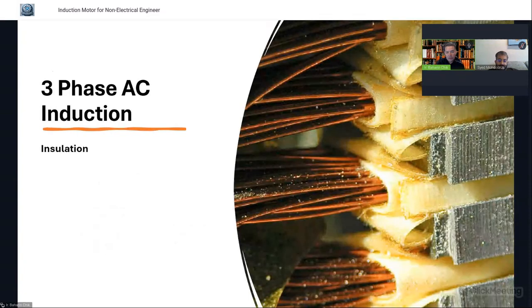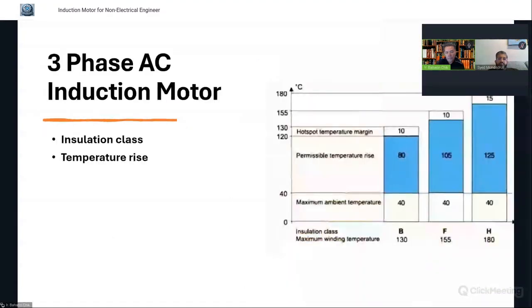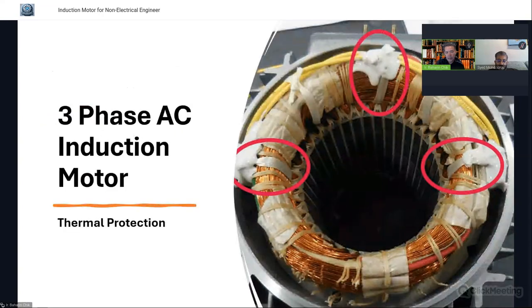Okay. So this shows the insulation of the motors, the white material that we saw in the beginning. And also for the motors, we have a temperature class and insulation class and temperature rise. We can have insulation class F and temperature rise class B, or we can have insulation class H and temperature rise class F. Okay, this is related to the amount of heat generated inside the motors, which needs to be taken out by the ventilation. And also we have thermal protection inside the motors. We have winding temperature detectors.